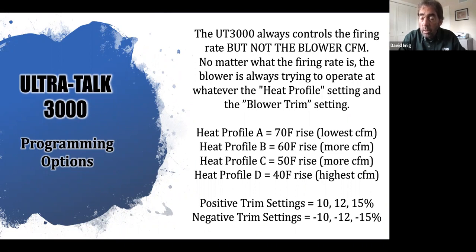So these blowers are based on 400 CFM per ton. In the setup, it allows you to give that a positive setting of plus 10, 12, or 15, meaning I could go up to 440, 450, or 460 per ton. It also allows me to lower that blower CFM and go negative 10, 12, 15, meaning I could take it down to 340 CFM per ton if I'm trying to lower the CFM at any given time during my operation, for one of my zones or for all of my zones.